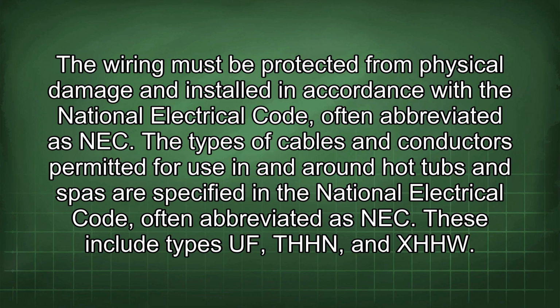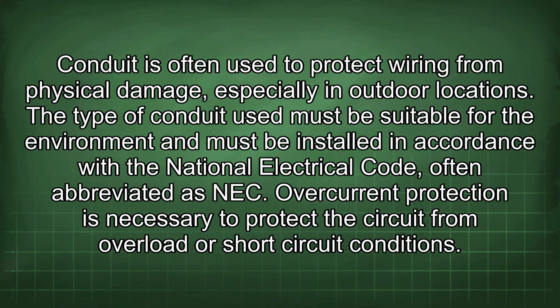The wiring must be protected from physical damage and installed in accordance with the National Electrical Code, often abbreviated as NEC. The types of cables and conductors permitted for use in and around hot tubs and spas are specified in the NEC. These include types UF, THHN, and XHHW. Conduit is often used to protect wiring from physical damage, especially in outdoor locations. The type of conduit used must be suitable for the environment and must be installed in accordance with the NEC.